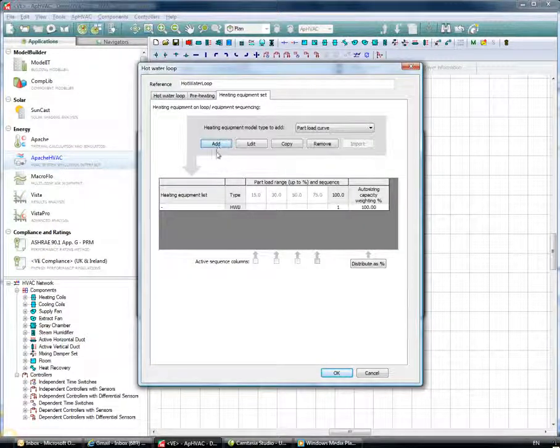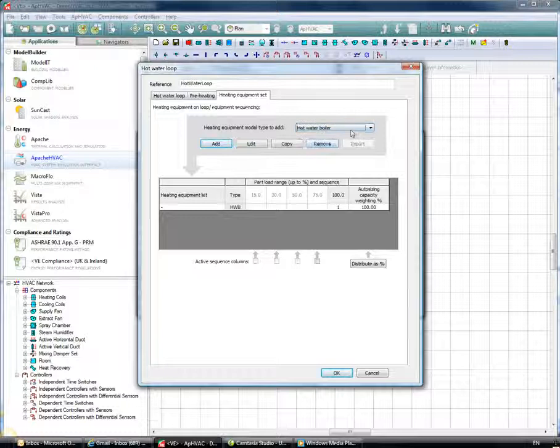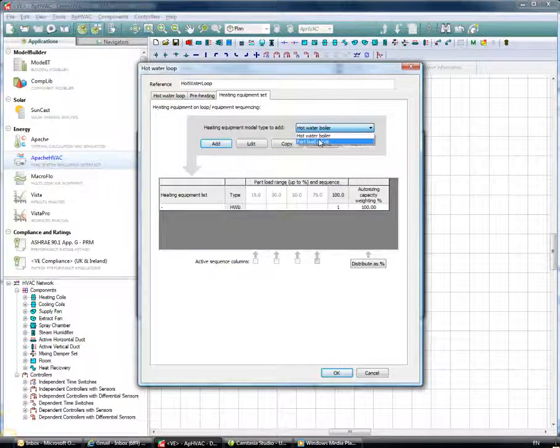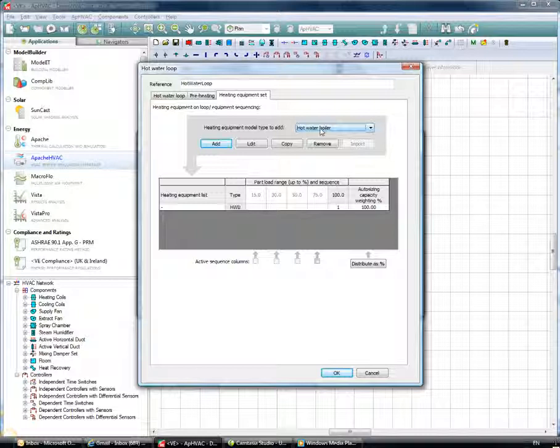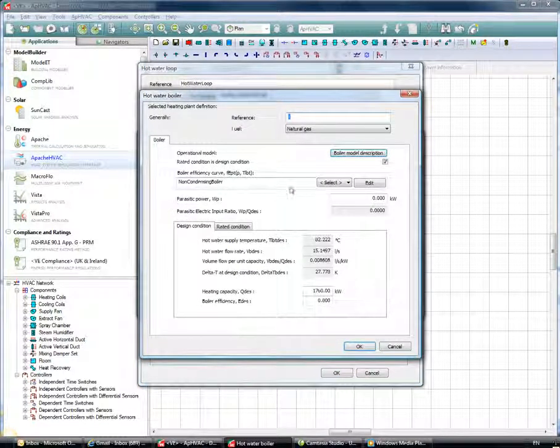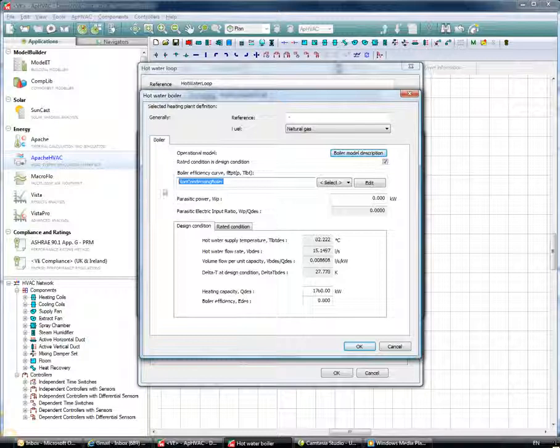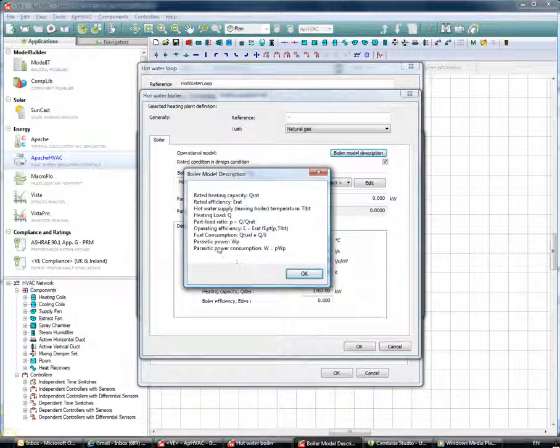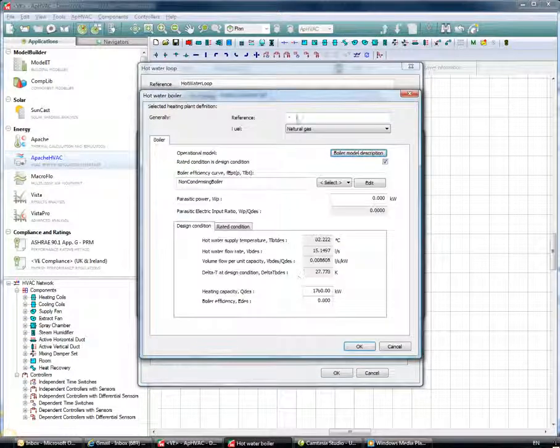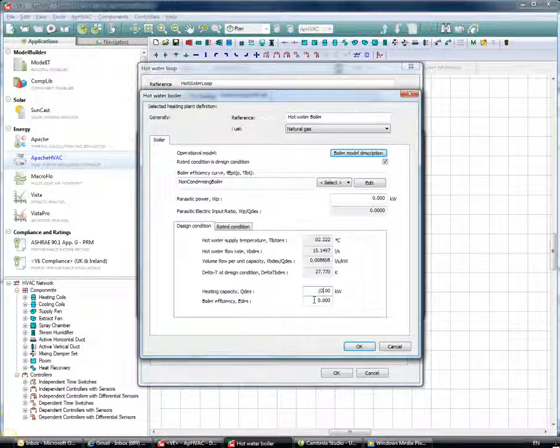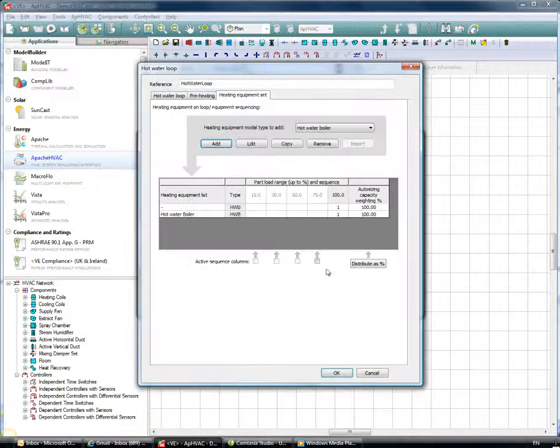The hot water loop allows us to model the details of the hot water side more thoroughly. We'll choose the hot water boiler, which allows us to select editable predefined curves — instead of defining a part load curve from scratch, we choose from predefined curves. In this case, we'll choose a non-condensing boiler. There's a boiler model description available to aid in your calculations. I'll call this 'Hot Water Boiler', set the heating capacity to 20 kilowatts, and set the boiler efficiency to 90%.